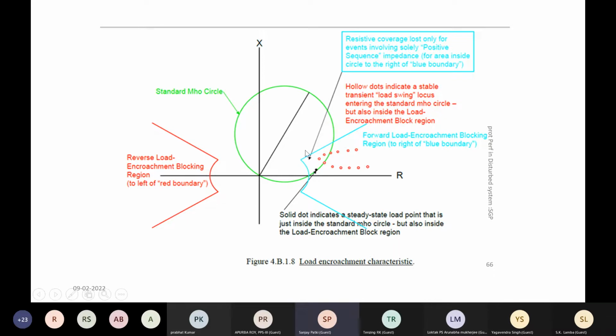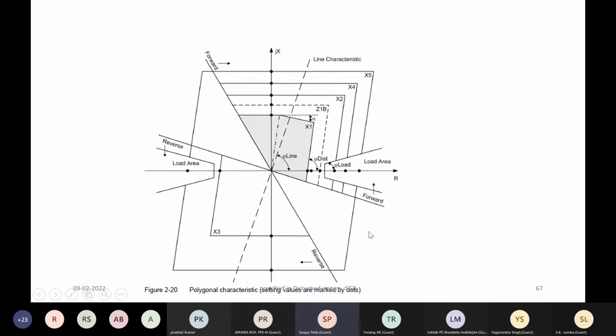Because when the fault takes place, the angle is likely to be very much reactive, almost 90 degrees, and usually the impedance point will be closer to the X axis and not closer to the R axis. The impedance due to load will be closer to the R axis, whereas impedance due to fault will be closer to the X axis. So that is the distinction the relay makes between load encroachment versus the fault condition. If you see the polygonal characteristic, similarly there is a load encroachment feature where this characteristic can be set, so that even if the load point enters this zone, the tripping is prevented.